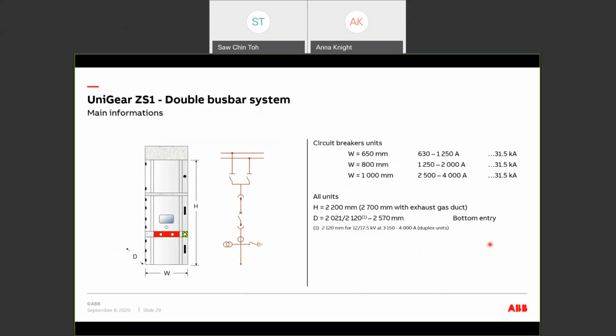The panel will have 2 sets of bus bar, running in parallel together with 2 sets of disconnector switch. Other than that, it has the same features as the UniGear ZS1 single bus bar panel, for example, the operation from the front of the panels as well as all the safety interlocks. The panel dimensions are either 650 wide, 800 or 1 meter, depending on the current rating. This type of cubicle has only the bottom cable entry option.